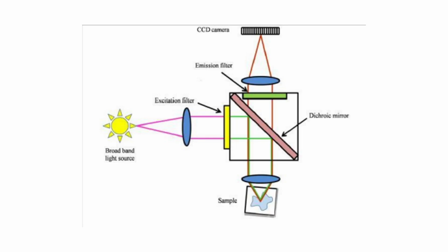Okay, so here this is the simple ray diagram of that. So we have a light source. Let's say I want to excite this sample here, so I'll use an excitation filter. An excitation filter is basically something that can filter a particular wavelength out. So that particular wavelength now will reach here. This is the dichroic mirror. It will hit the dichroic mirror and get reflected. Okay, it's a mirror. It will reflect the light beam, and the light beam falls on the sample.